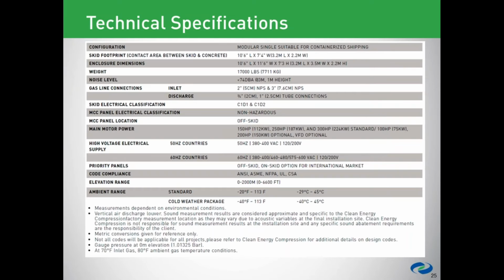And then the final thing is a safety consideration. The compressor package is designed for the worst case of a component blowing loose. The wall panels are designed to take the impact and severely mitigate the effect of that, whereas without that, we generally recommend that there's a barrier or something preventing the public from accessing this package.